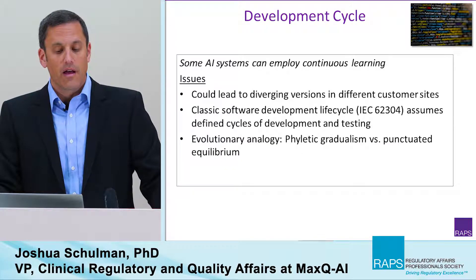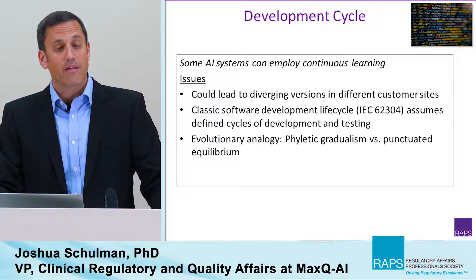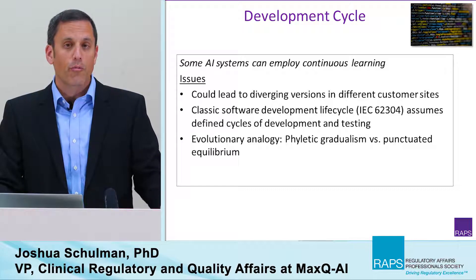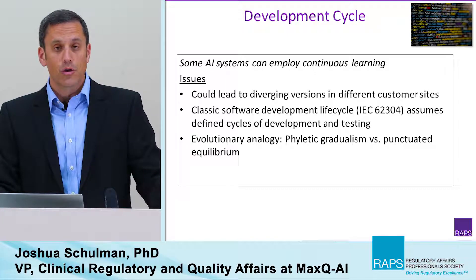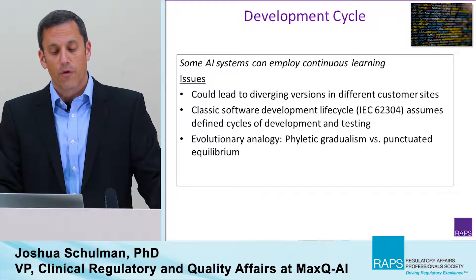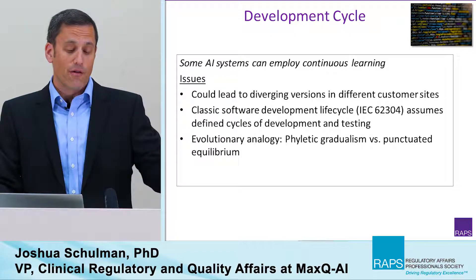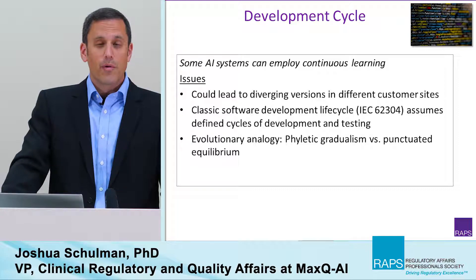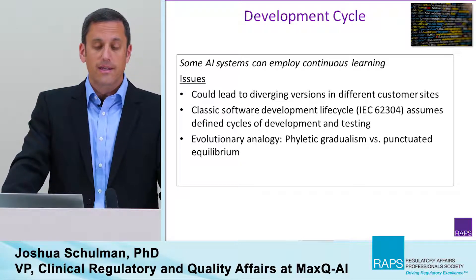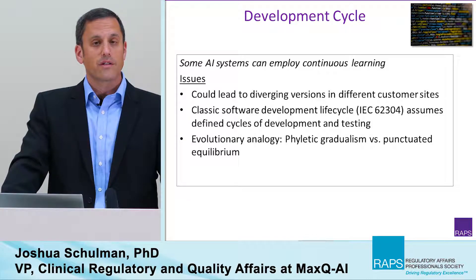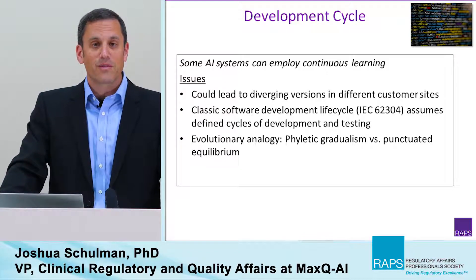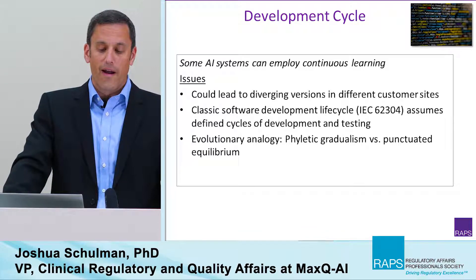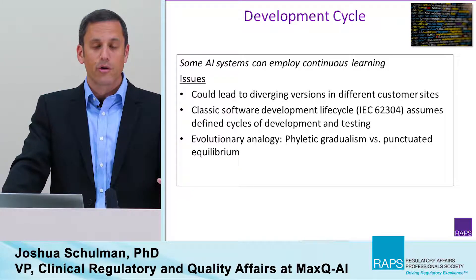In addition, when thinking about the development cycle of a device, one key feature of AI devices is that many of them can employ continuous learning. An AI device can be capable of learning from its errors, of incorporating new data as new data becomes available to it from use in the clinical space. This raises a number of issues for medical device development. First of all, it raises a theoretical issue of diverging versions at different customer sites, which is a quality and monitoring challenge. But more fundamentally, the classic software development cycle in IEC 62304, the software development life cycle, assumes defined cycles of development and testing. If we were to think about this with an evolutionary analogy, AI devices are capable of phyletic gradualism, whereas the IEC 62304 standard really assumes punctuated equilibrium.